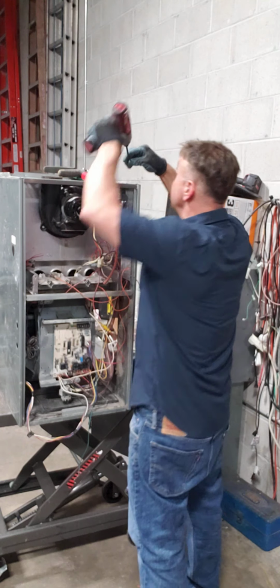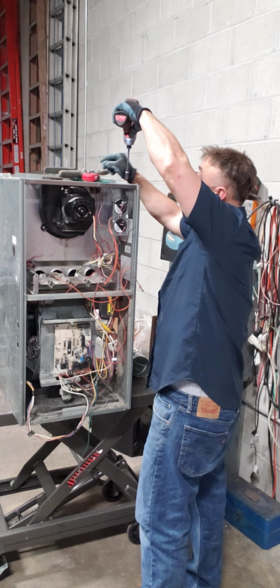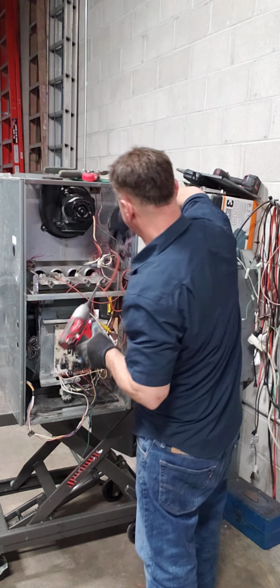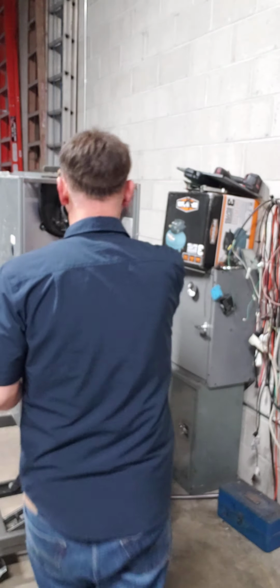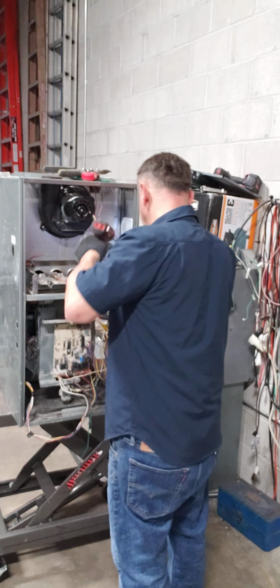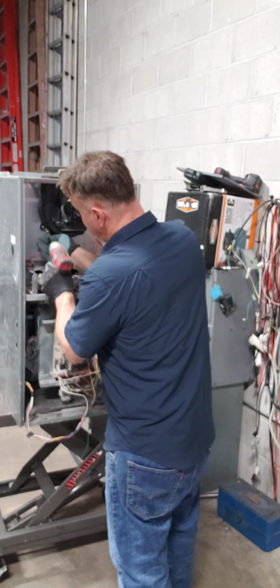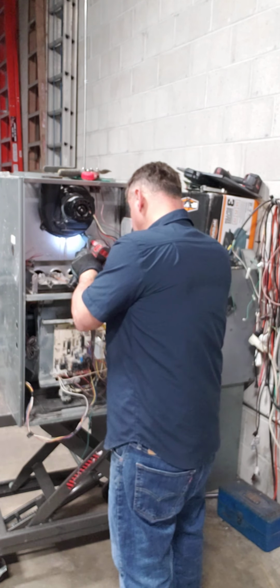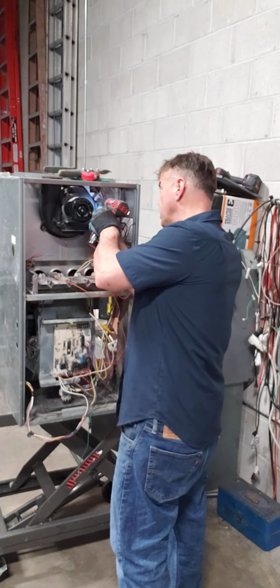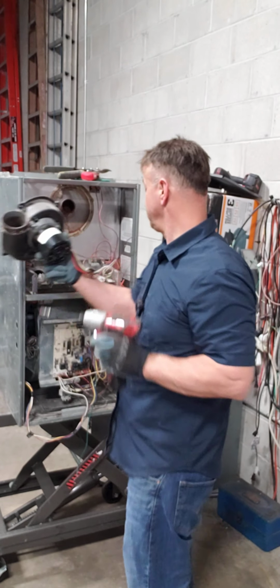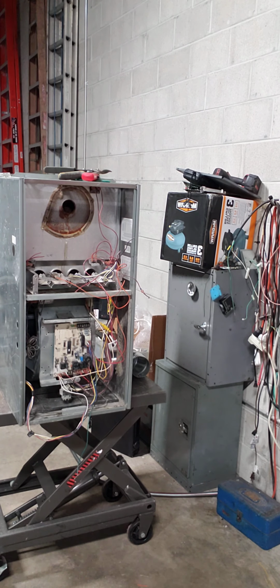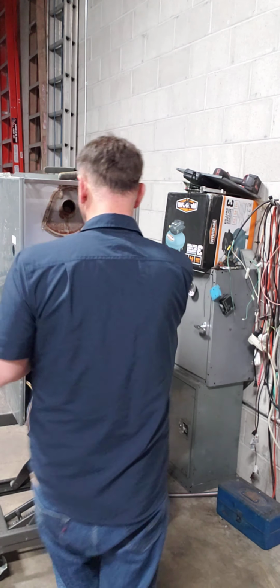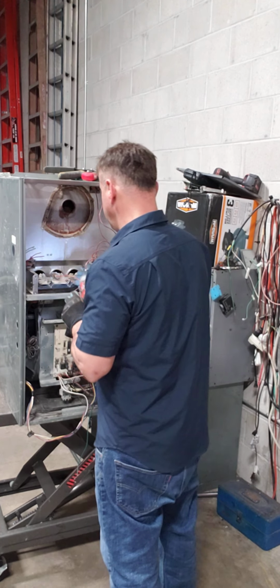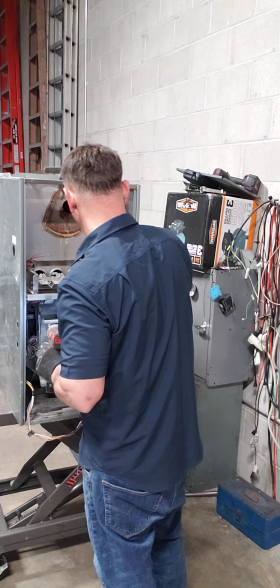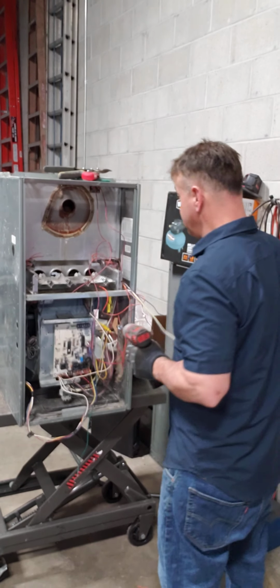Now the pressure switch, as I was saying earlier, there are two screws, and this is the pressure switch, right? There are two screws, and it's out. Now the inducer motor, as I showed you earlier, is very easy to remove, right?